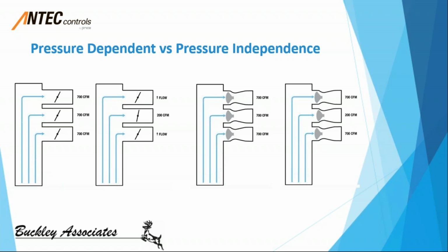In a pressure dependent system, which is what we're going to look at over here on the left side of the screen, the airflow through the valve, these are just dampers here, is dependent on the pressure in the ductwork. We have three VAV boxes here, or let's say they're dampers, all allowing 700 CFM through apiece. If the airflow requirement to this middle space is reduced to 200 CFM, what's going to happen to the pressure in the ductwork? It's going to increase. Therefore, if we don't adjust the other dampers, the flow through those dampers is going to increase. So if we block off this damper, the flow is going to increase in both of these valves.